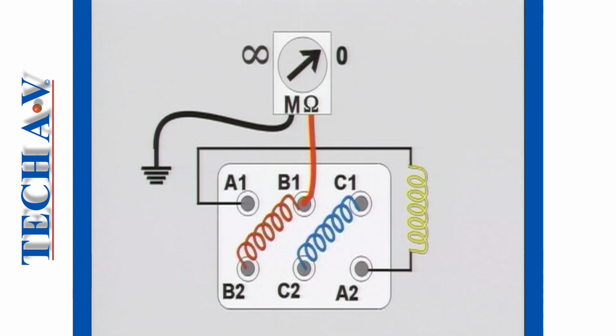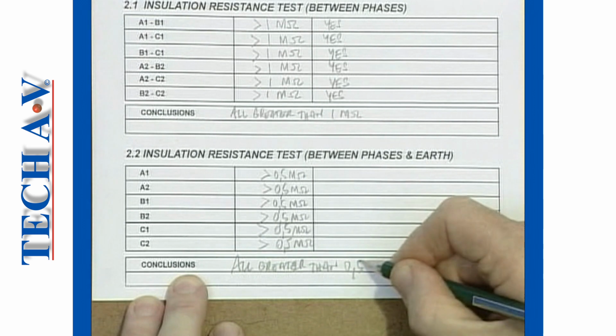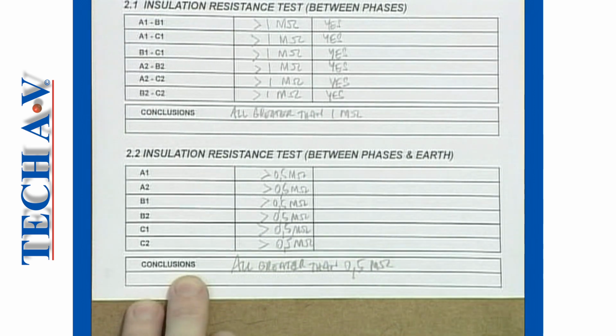Any reading less than half a megohm suggests a possible insulation breakdown in the electrical system to earth. After the break, we will return to discuss the mechanical test procedures.